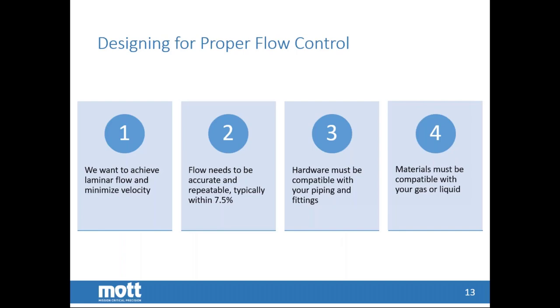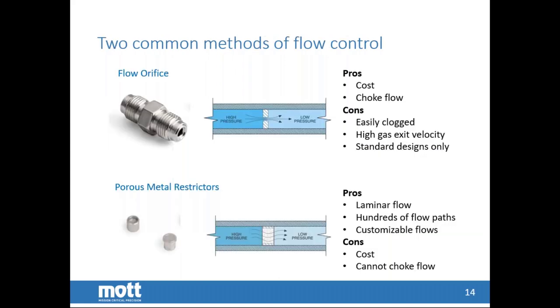For flow control, what we're looking for is to achieve a laminar flow through the porous. Our standard accuracy is plus or minus seven and a half percent. We can go down to as much as plus or minus two percent in accuracy. Obviously, the hardware must be compatible with the application and the piping or the plumbing, the fittings, as well as the material must be compatible with the gas or liquid. There are two common methods for flow control: one is a flow orifice, which is basically a single hole through a disc, and the other would be our porous metal material.